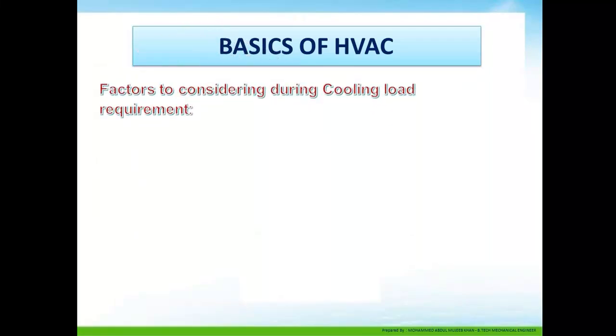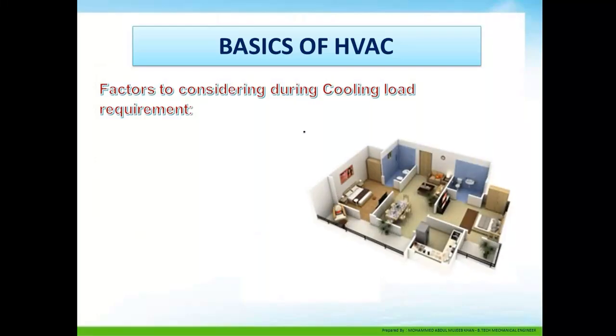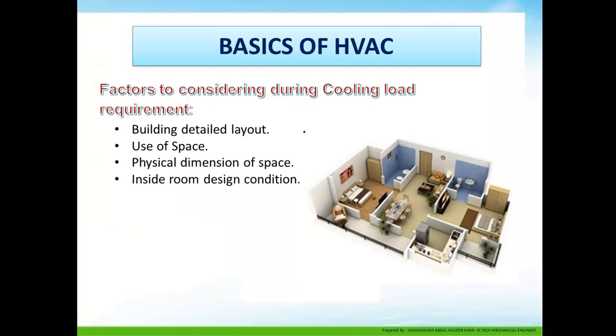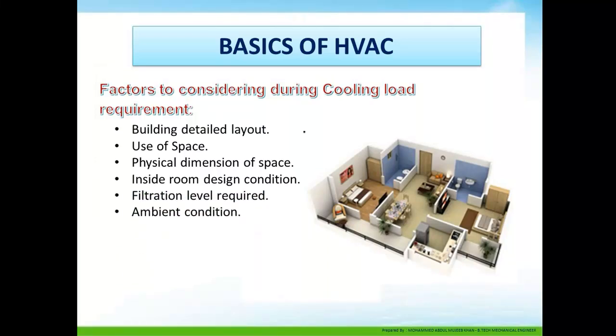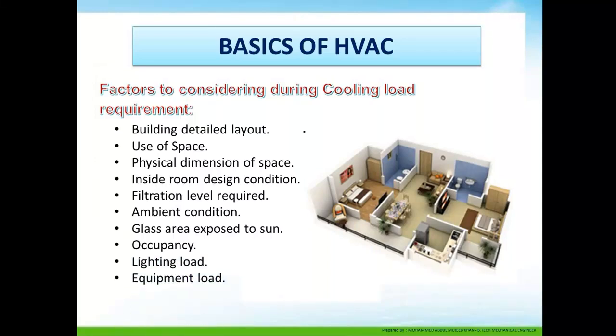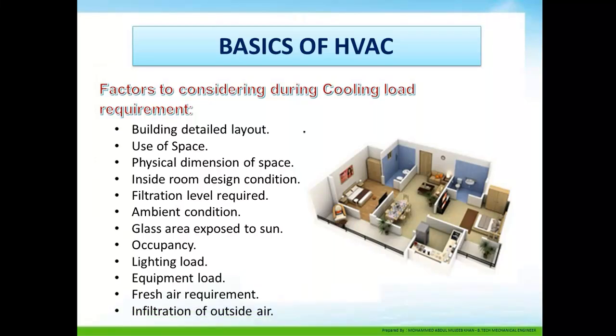Factors to consider during the cooling load requirement: building detail layout, use of the space, physical dimensions of the space, inside room design condition, filtration level, ambient condition, glass area exposed to sun, occupancy, lighting load, equipment load, fresh air requirement, and infiltration of outside air.